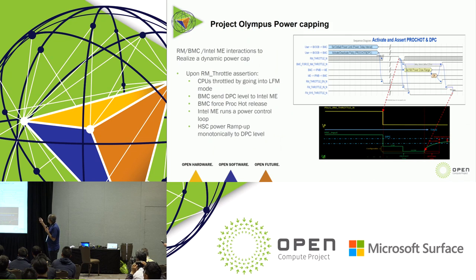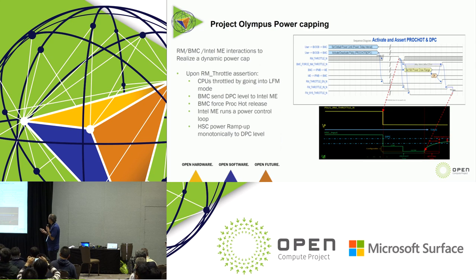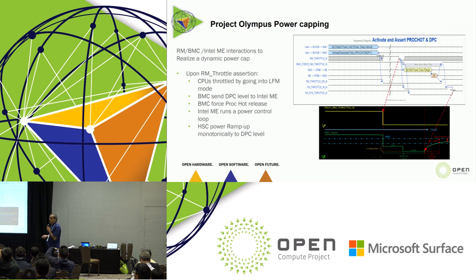There is a timing diagram showing the interaction between the BMC, rack manager, and Intel Node Manager to realize power capping. As soon as the proc hot or RM throttle is asserted, we go to low frequency mode and set the policy to Intel Node Manager. After that, Intel Node Manager takes over and ramps up to the newly defined policy.